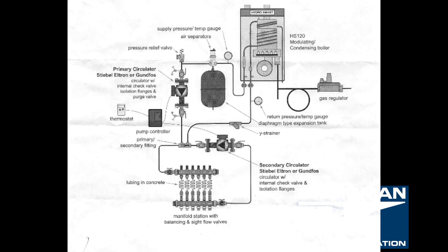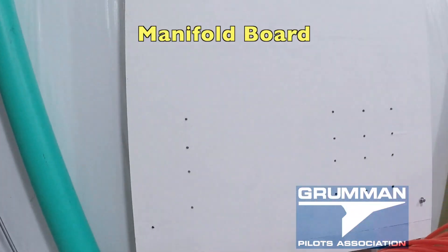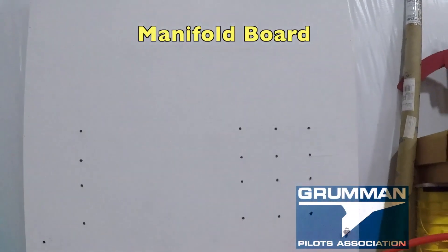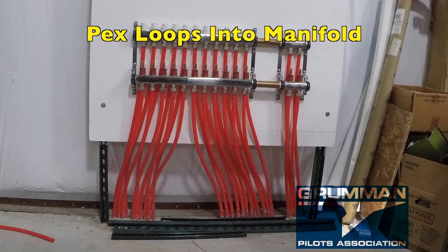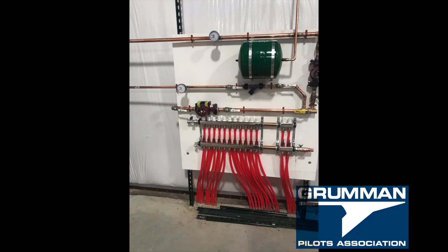We designed our system based upon the Hydro Smart diagram that came with our boiler. We laid out a manifold board to corral all the PEX tubing into the manifold, both the supply and the return lines. There are 26 pieces of PEX and 13 loops; the two on the right are for the radiant ramp.